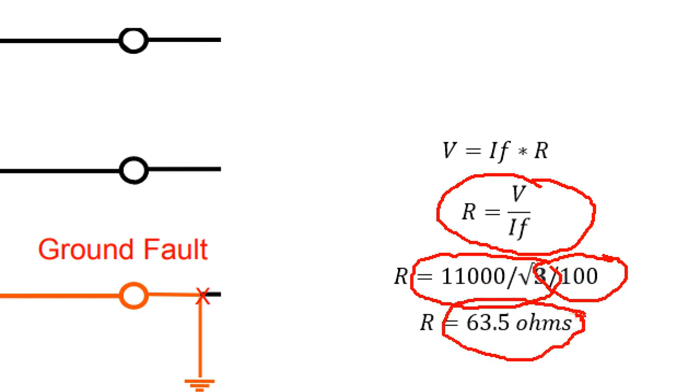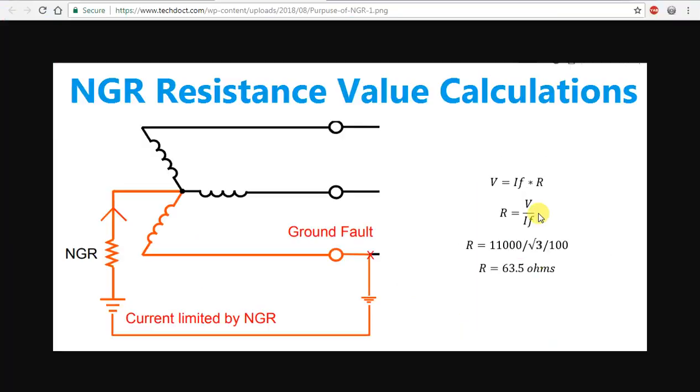This is the value of 63.5 ohms for single phase. So we calculate the resistance value as V, the phase voltage, divided by the fault current.